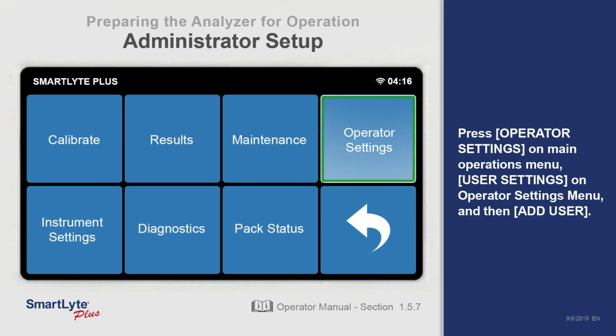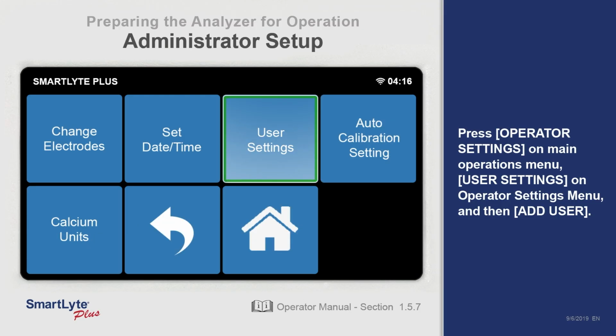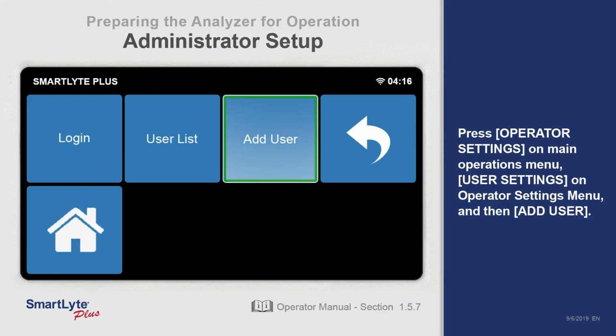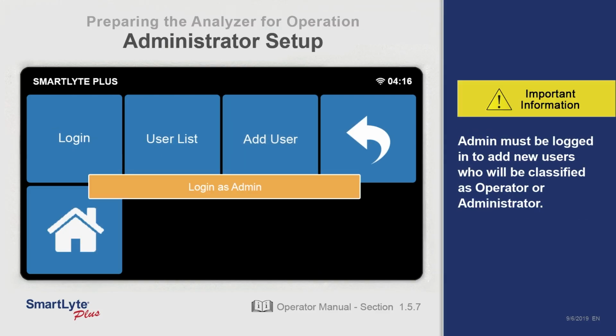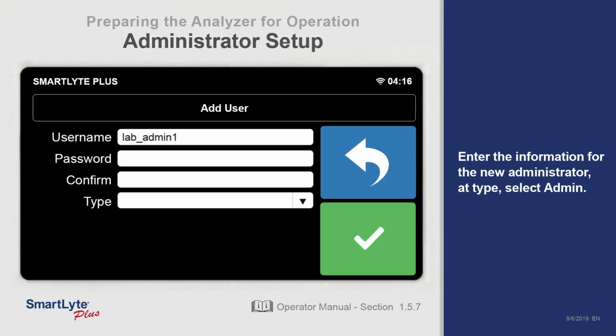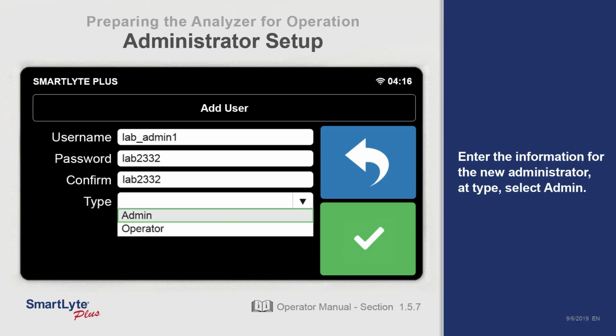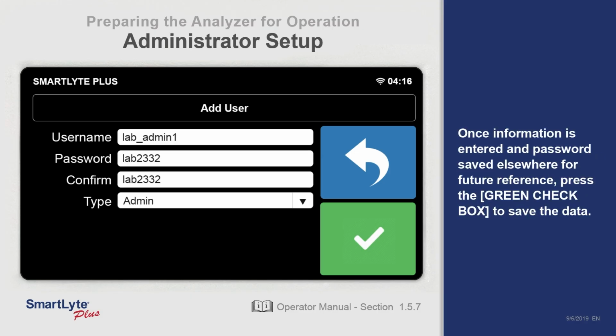Press Operator Settings on the main Operations menu, User Settings on the Operator Settings menu, and then Add User. Admin must be logged in to add new users who will be classified as operator or administrator. Enter the information for the new administrator. At Type, select Admin.